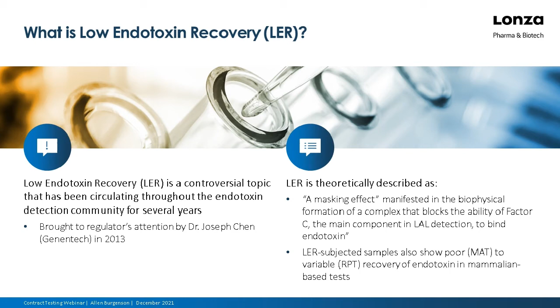So now we'll get to the issue of low endotoxin recovery. LER is a controversial topic that's been circulating since 2013 when it was brought to FDA's attention by Dr. Joseph Chen. It's theoretically described as a masking effect manifested in biophysical formation of a complex that blocks the ability of factor C to bind to endotoxin. So if factor C cannot see the endotoxin, it can't react with it. What also must be understood, though, is that if factor C can't see it, neither can TLR4 on the cells. And LER subjected samples also show poor MAT variability for the same reason. The cell surface receptors cannot see it.